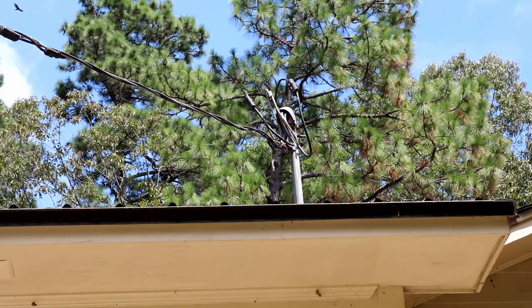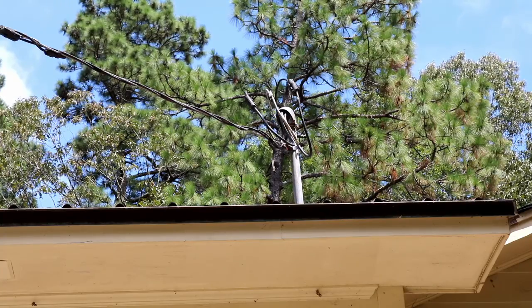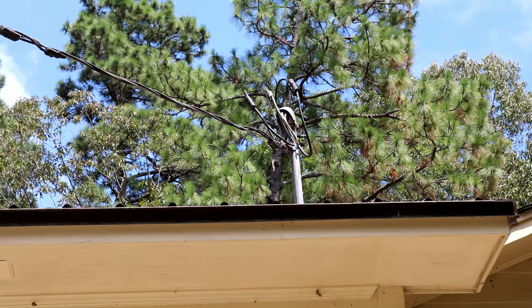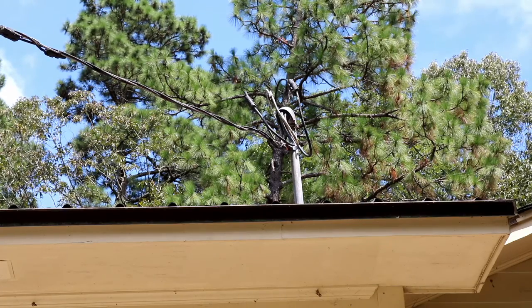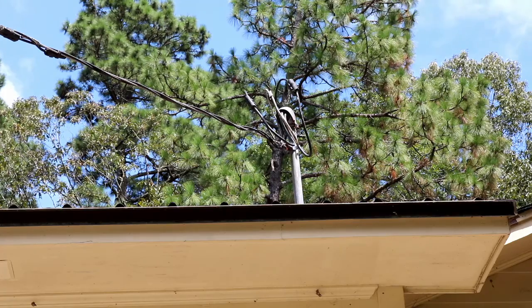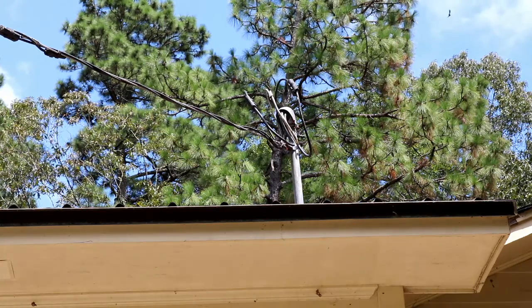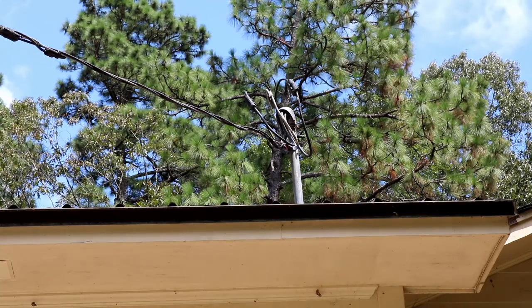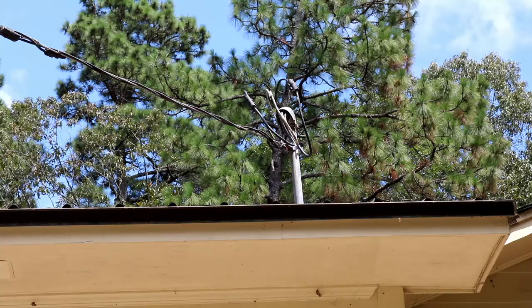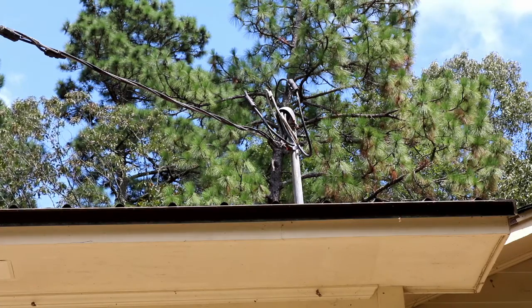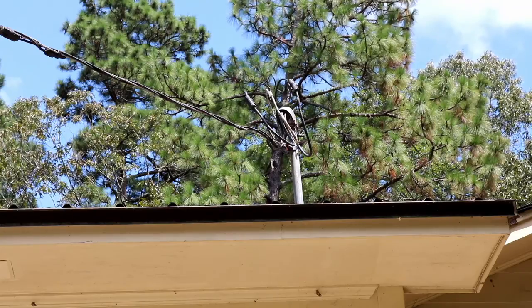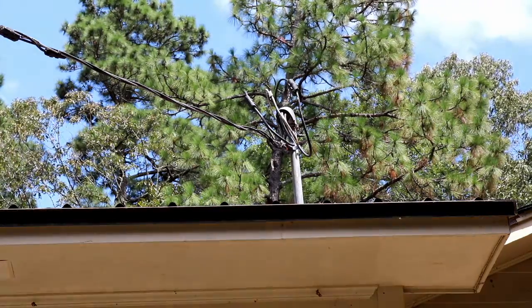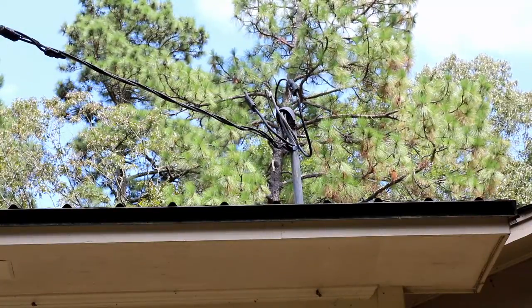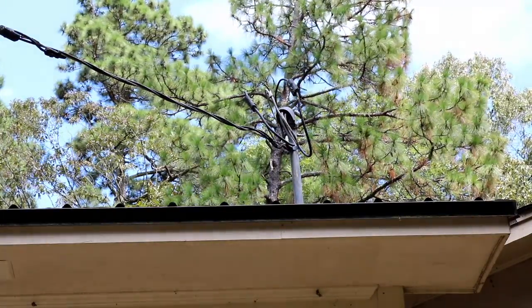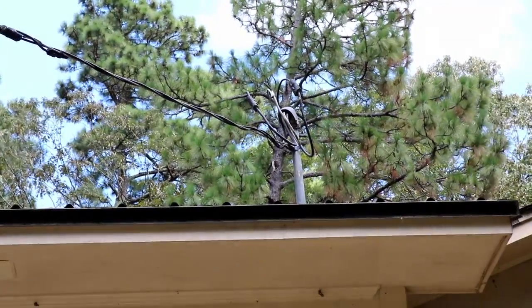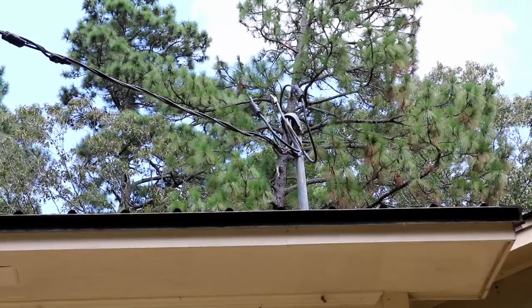If you measured the voltage between one of the insulated conductors and that bare neutral conductor, you'd get 120 volts. If you measured between one insulated conductor and the other insulated conductor, you'd get 240 volts. So that's strung from that transformer—this triplex goes from the transformer out by the road right into that weatherhead. Now I'll take you over to show you where it goes from there.